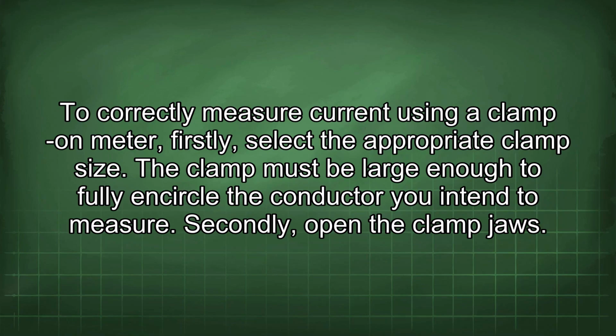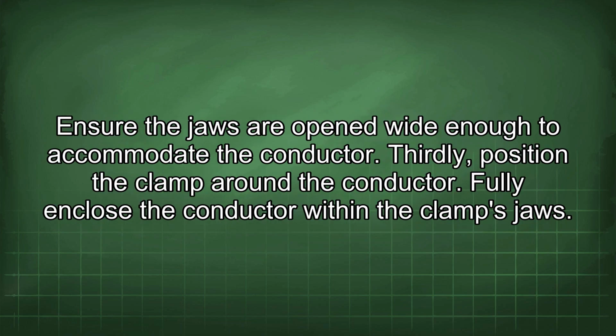To correctly measure current using a clamp-on meter, firstly, select the appropriate clamp size. The clamp must be large enough to fully encircle the conductor you intend to measure. Secondly, open the clamp jaws. Ensure the jaws are opened wide enough to accommodate the conductor. Thirdly, position the clamp around the conductor. Fully enclose the conductor within the clamp's jaws.